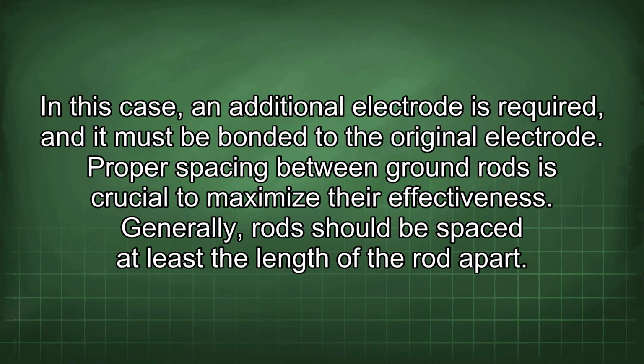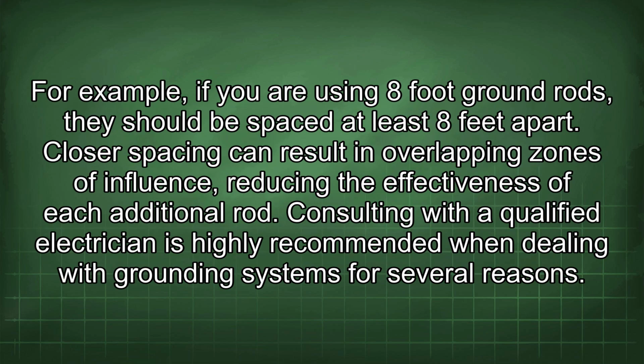Generally, rods should be spaced at least the length of the rod apart. For example, if you are using 8-foot ground rods, they should be spaced at least 8 feet apart. Closer spacing can result in overlapping zones of influence, reducing the effectiveness of each additional rod. Consulting with a qualified electrician is highly recommended when dealing with grounding systems for several reasons.